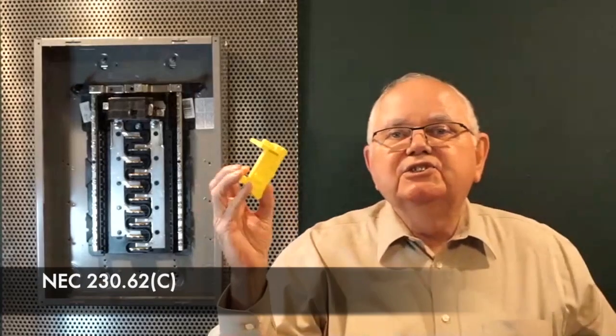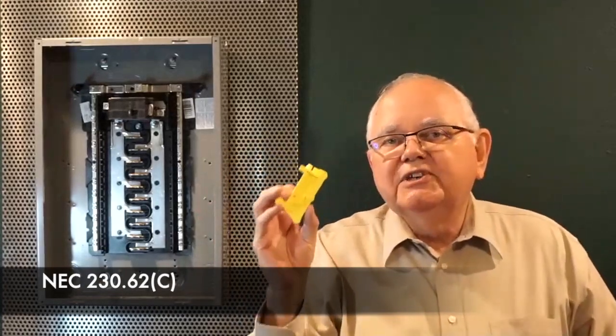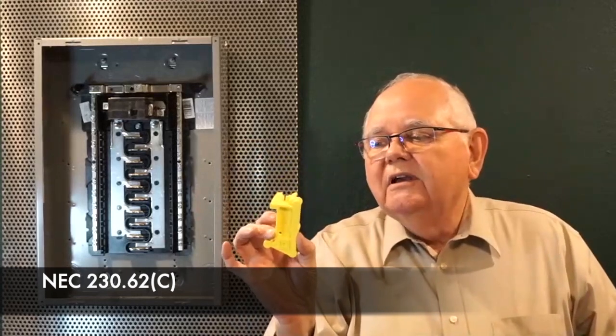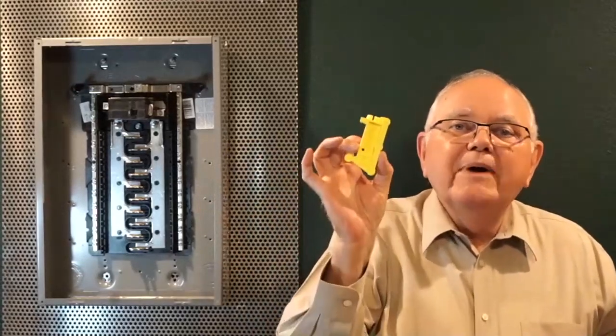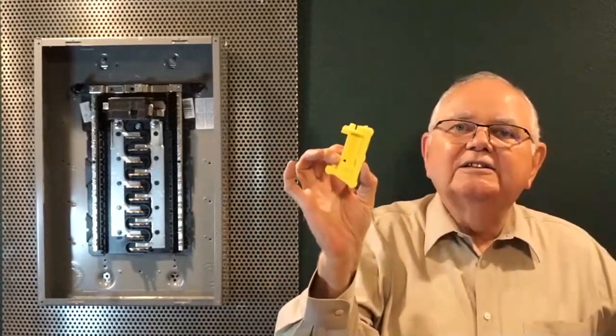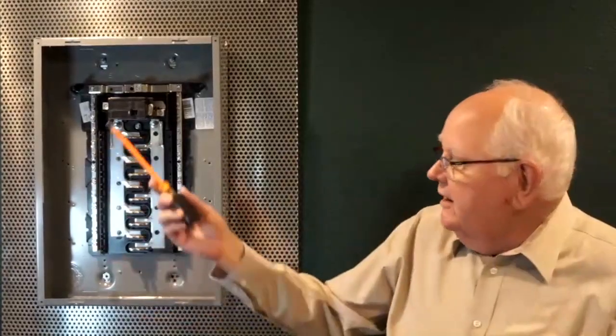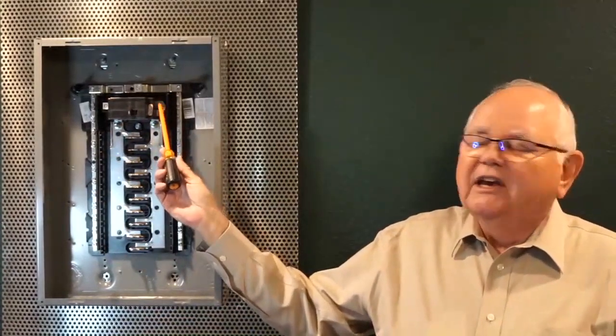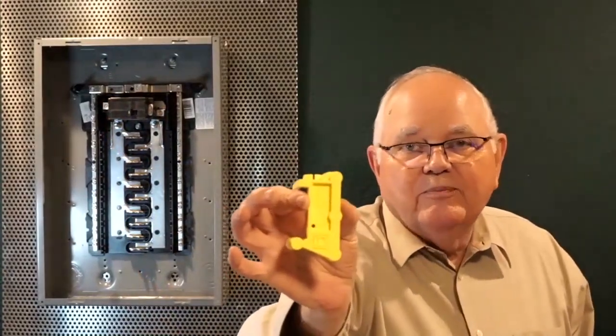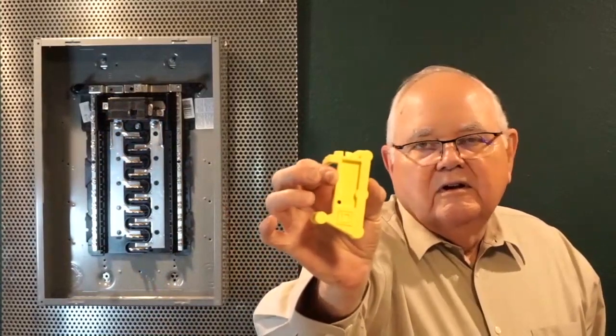Now, if I have something like on a service panel, by the way, 230.62(C) of the NEC, there's a 2020 requirement now, it's new for the 2020, that requires on service equipment that I have this barrier in place. The purpose of the barrier is to prevent inadvertent contact on my service equipment with the incoming service bus bars or service conductors. So if this were a service panel, and I were going to terminate my service conductors, in this case on either side of the main breaker, I would have to install one of these little plastic caps or barriers, as they call it, over those termination lugs.